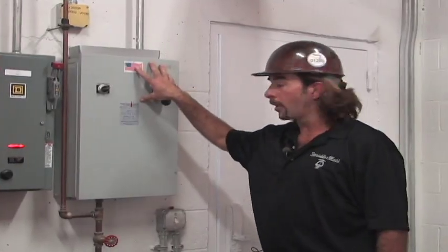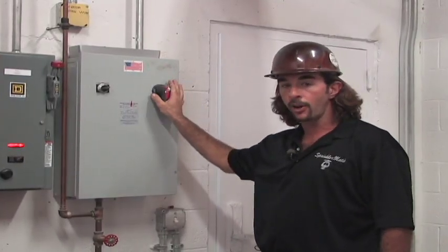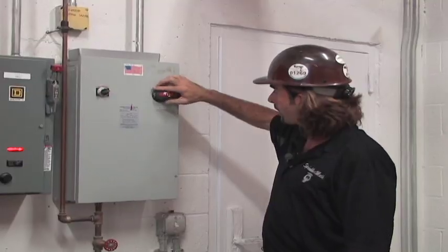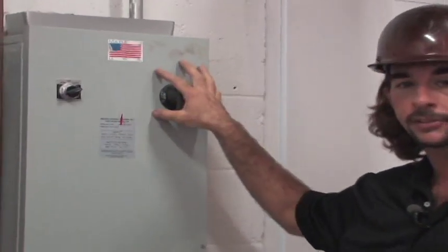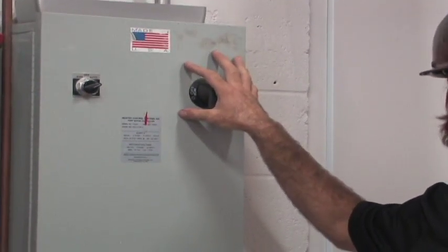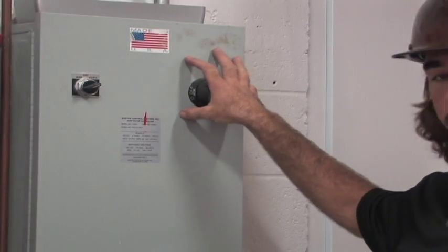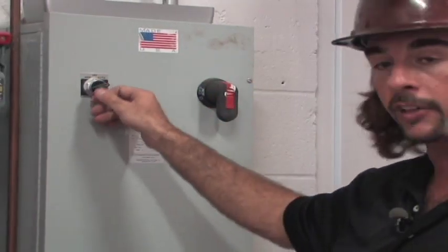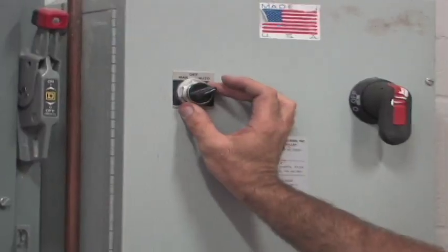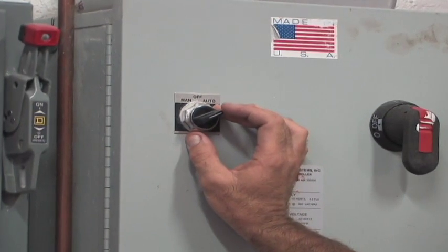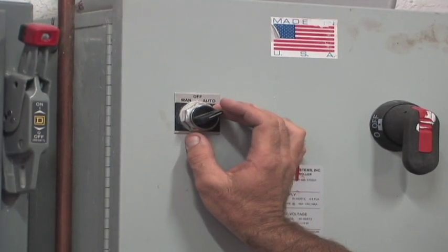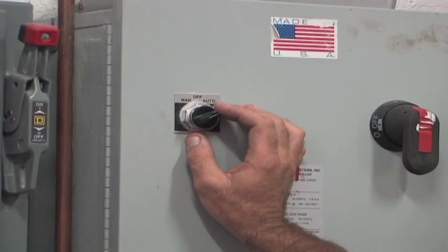Our jockey pump controller. We have our main on and off switch. Naturally, this is going to be in the on position, 24/7, 365. This is always going to be on. We have our selector switch. We have auto, which means the jockey pump is going to work strictly by loss of pressure. Whenever it gets below 160, the jockey pump is going to kick on, and it's going to turn itself off at 180, just with the pressure switch that's inside here.